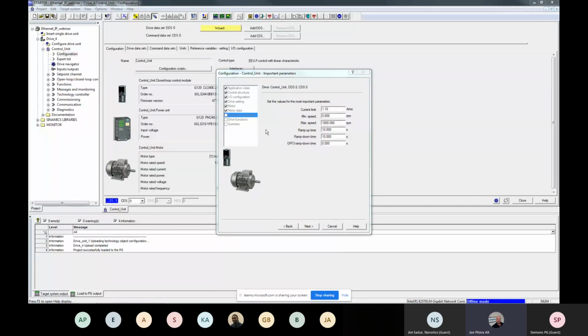We are going to change the ramp times for our demo here to 3 seconds. And we are going to leave the max speed at 1800 RPMs. And we are going to take the off 3 time to 1 second. Off 3 is the fast stop or quick stop time ramp when you want to use an off 3 command.